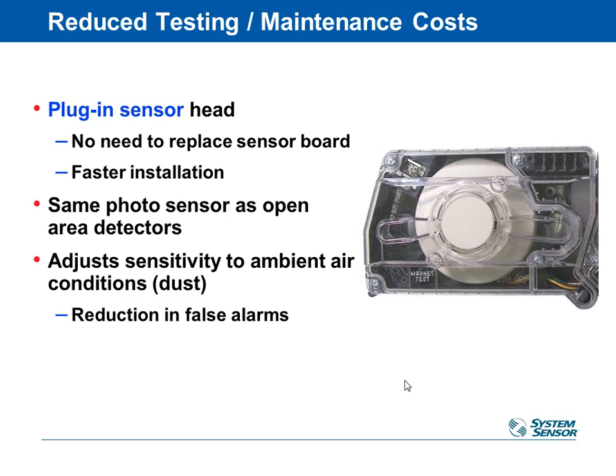If you do need to ever change out one of the sensor heads, that's the white piece that's underneath the plastic cover here, they are actually the same sensor heads that are used in the occupant spaces and the ceiling type systems. So if the fire guy has those or stocks those, he can easily put one into one of these guys as a replacement. So it's not like it's two separate things. It's very easy to swap out. All the boards and wiring can stay the same.